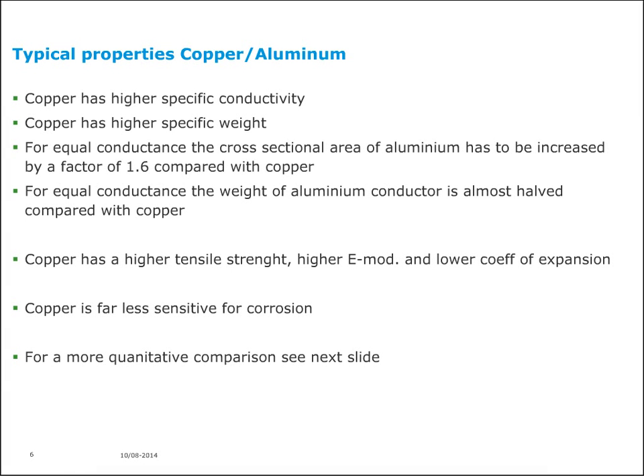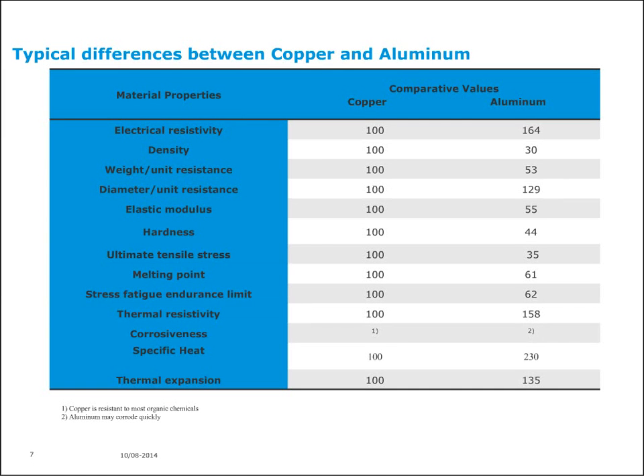For a more quantitative comparison, I'd like to show you the next slide. Here I've given copper the value of 100, and the other value is given on a relative scale. First, electrical resistivity: when copper is 100, aluminum is 164. Density goes the opposite way: when copper is 100, aluminum's density is 30, much less in weight. Looking at weight in relation to unit resistance, the values are 100 and 53. Looking at diameter in relation to unit resistance, it's 100 and 129.